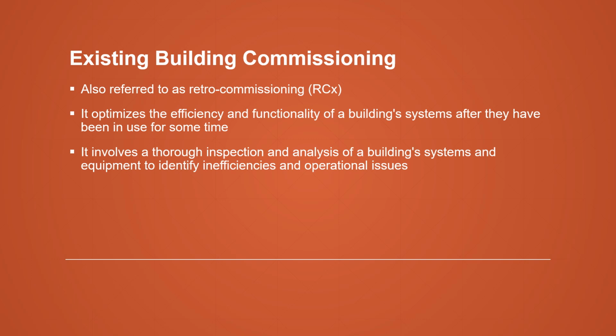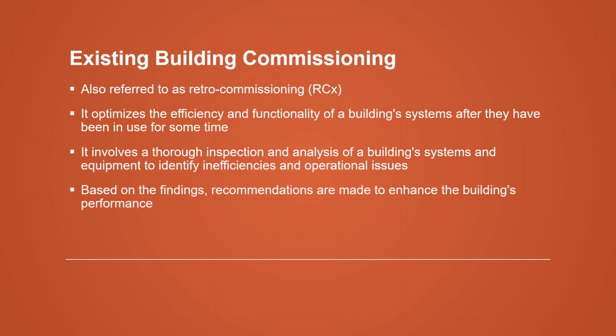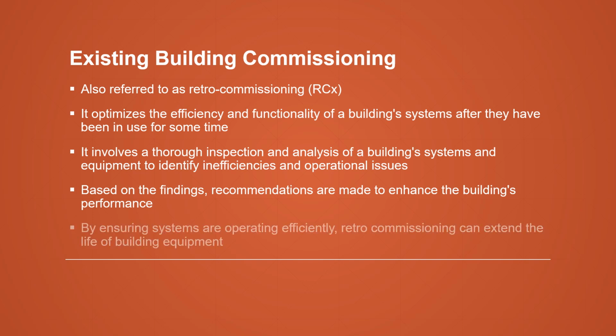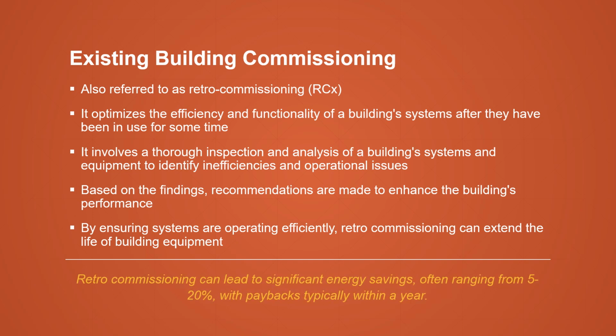Retro-commissioning involves a thorough inspection and analysis of a building's systems and equipment to identify inefficiencies and operational issues. Based on the findings, recommendations are made to enhance the building's performance, which can include fixing air leaks, upgrading HVAC systems, and improving lighting. By ensuring systems are operating efficiently, retro-commissioning can extend the life of building equipment. Why invest in retro-commissioning services on an existing building? Retro-commissioning can lead to significant energy savings, often ranging from 5 to 20%, with paybacks typically within a year.